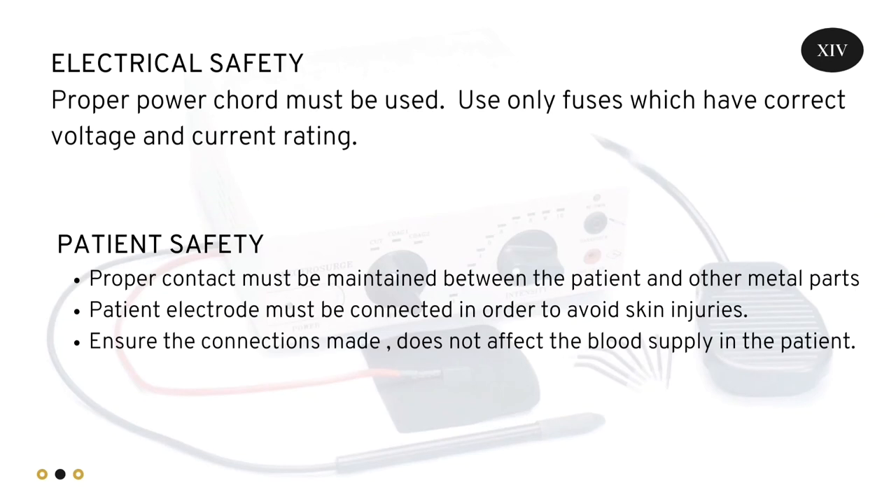Electrical safety: Proper power cord must be used. Use only fuses which have the correct voltage and current rating. Patient safety: Proper contact must be maintained between the patient and other metal parts. Patient electrode must be connected in order to avoid skin injury. Ensure the connections made do not affect the pacemaker or inner patient devices.